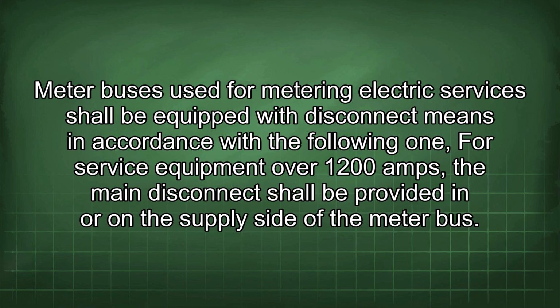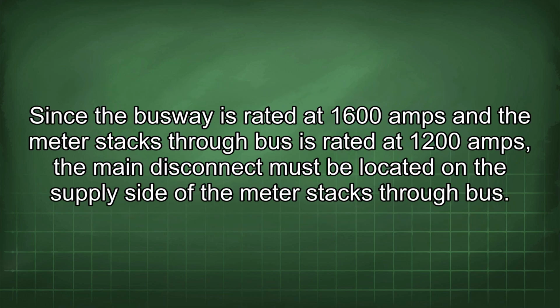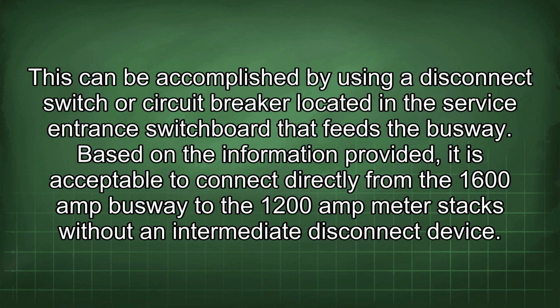of the meter bus. Since the busway is rated at 1600 amps and the meter stacks through bus is rated at 1200 amps, the main disconnect must be located on the supply side of the meter stacks through bus.